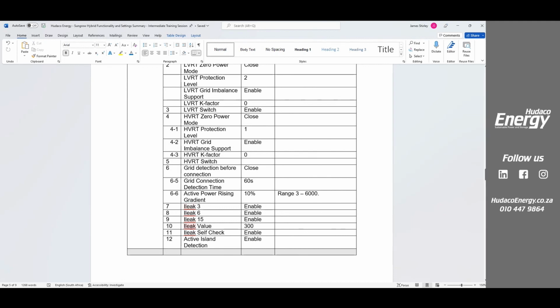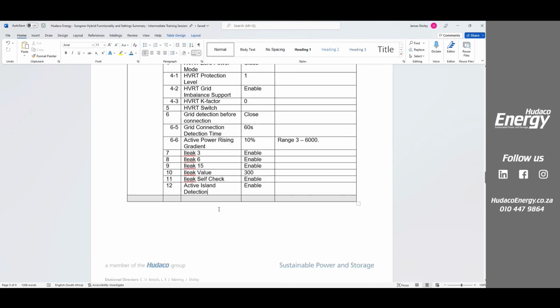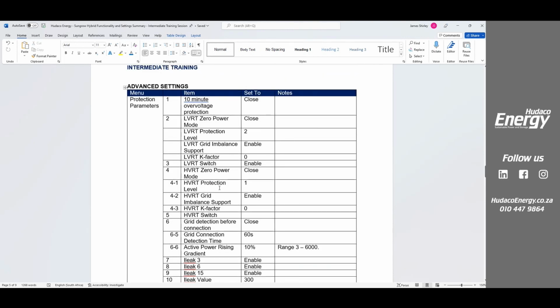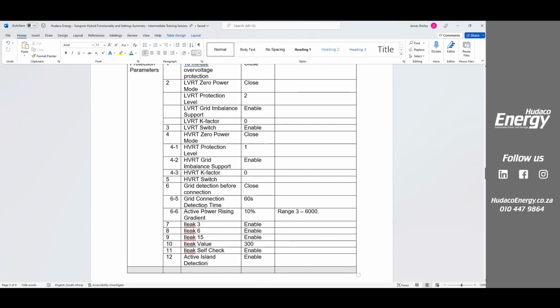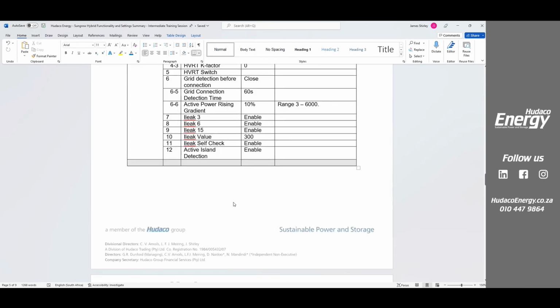This I leak stuff here. This is basically earth leakage. So this is your current leakage. We can control 30, 60 milliamps, 150 milliamps. 300 is the normal value that we use for South Africa. Are we doing a self-check on current? You know, are we doing active island detection or passive island detection? So all of these things are options. It's an incredibly powerful system, and we have a lot of control over a lot of things.